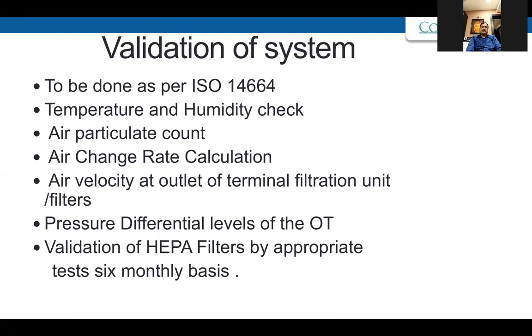A validation of HEPA filters on a 6-monthly basis. Most of them are doing it on a yearly basis. So this change has been made in the last edition, which was taken out, that 6-monthly validation should be done for HEPA filters in terms of integrity as well as the particle count.